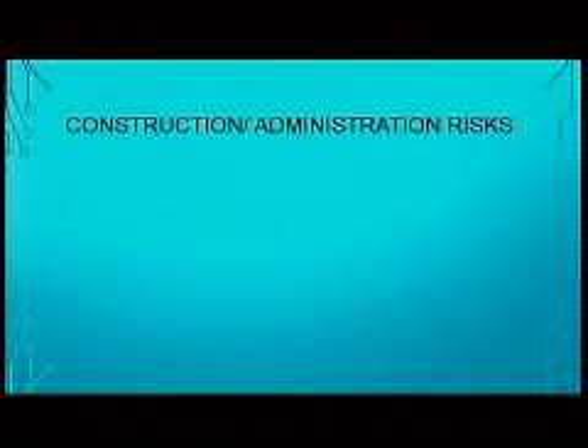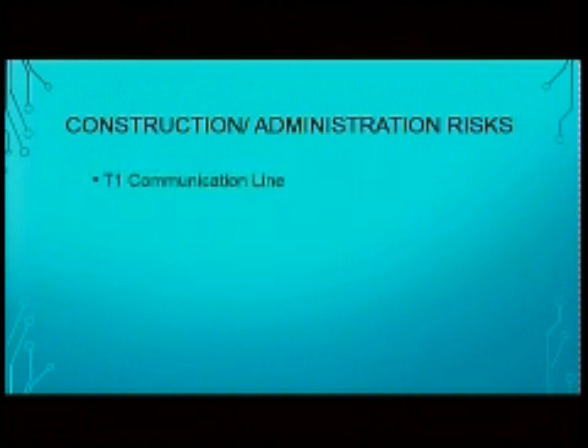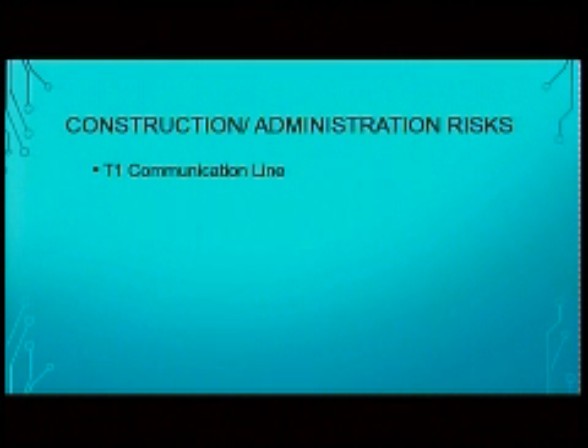So, construction and administration risks at this point: the T1 communication line, to put it simply, is a line from KM Green to Stockton required by PG&E. Since this line has nothing to do with the district, we requested that PG&E place the order and pay for it, but were refused. This line is needed for PG&E to complete end-to-end testing on the 3-way protection scheme. The line is actually already installed, but due to an error it was placed in the wrong channel down in Stockton. We are now waiting for it to be moved to the correct channel, hopefully on 10/17. The order was originally placed in April.